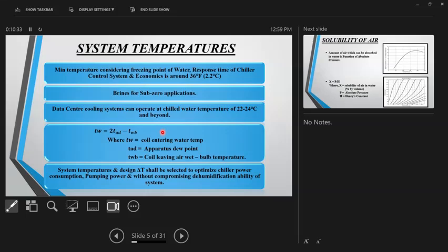Regarding data center cooling systems, you mentioned chilled water temperature of 22 to 24 and beyond. Right now we are looking at a data center at around 24 degrees, say with 50% RH, or 50 to 60% RH. When I want to maintain 24 or 22, of course my chilled water temperature should be around 7, 9 or 10 degrees. If I maintain 22 degrees as the chilled water temperature, my data center temperature will go to 30 degrees. Correct. So data centers nowadays operate at even 30, 35 degrees centigrade air temperature inside.